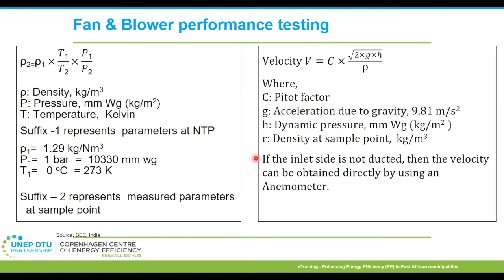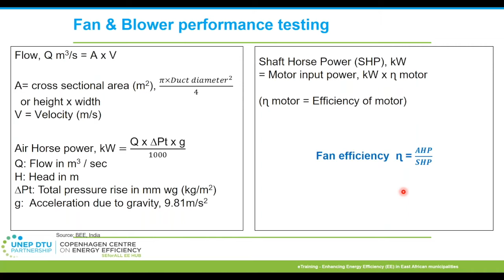Similarly to pump curves, you can also ask your supplier for fan curves if you think these measurements are quite complex, or you don't have the intention to carry out detailed measurements. You can always ask for the fan curves from your supplier, then have a look to roughly estimate the different parameters at which the fan or blower is operating.